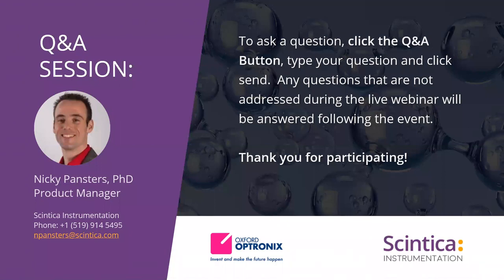Percentage-wise, I would definitely say no with reference to barometric changes in weather, or even altitude changes, if you're literally working in Switzerland in the mountains versus somebody in the Netherlands like me, where half of the country is below sea level. So in that respect, you do need to account for barometric changes, and if you work on % oxygen, it has been calibrated on something. Therefore, it's always important to understand how your system works, what it's calibrated on, and how it's attempting to regulate its oxygen content. On average, I would suggest to try to see not percentage, but millimeters of mercury or kilopascals as the gold standard to work with in the future.